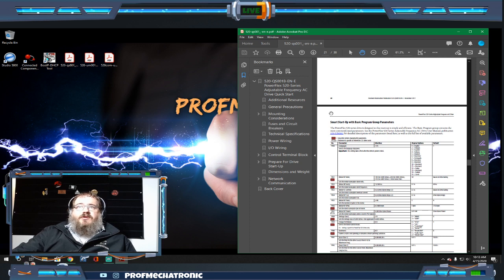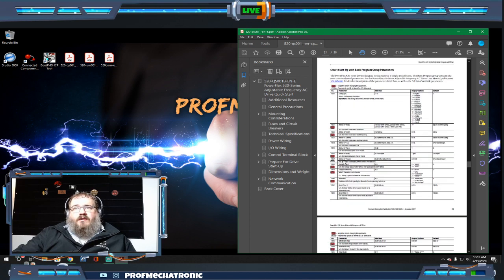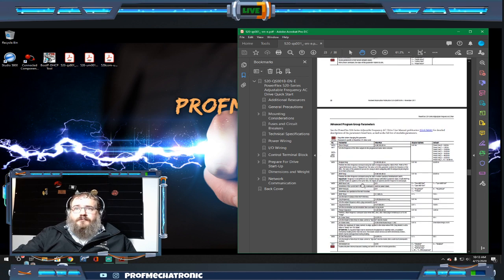Make sure when you're doing any of the smart startup and basic programming under P that you have stopped the drive. They call out which ones need to be stopped in order to change on the drive. You can change some of these parameters live as you go, so you want to keep your eyes on that.